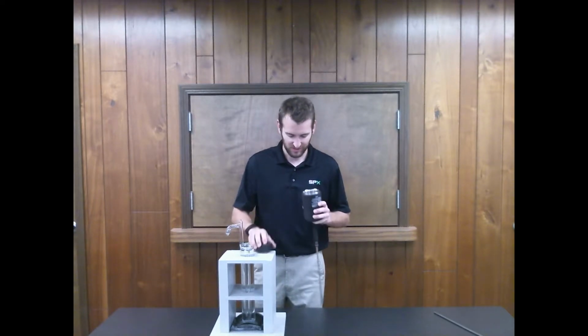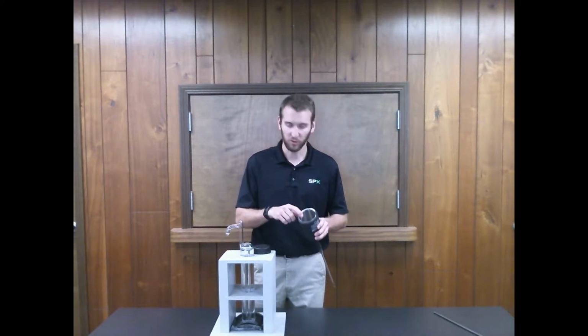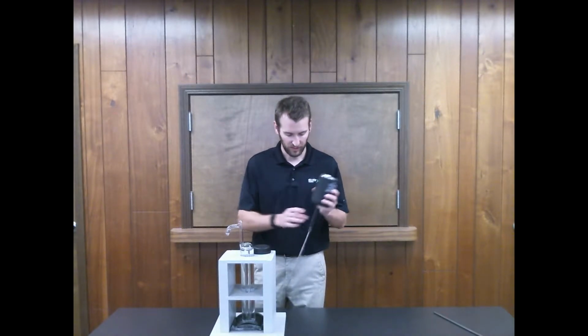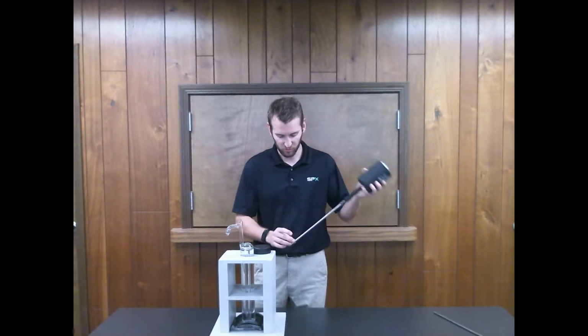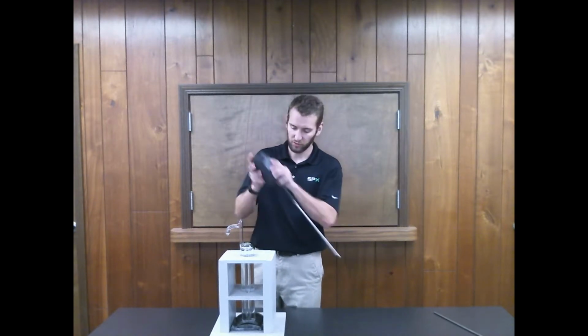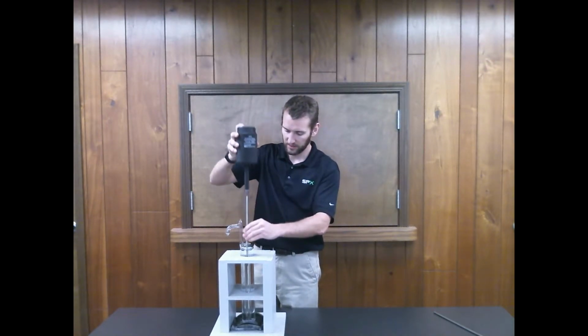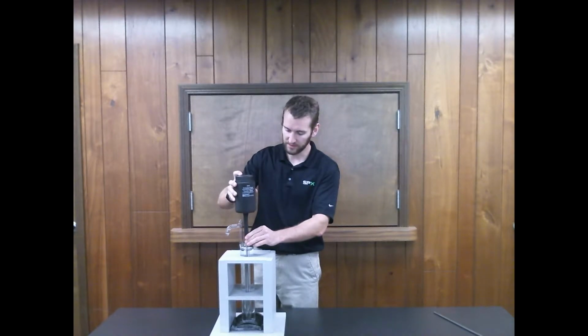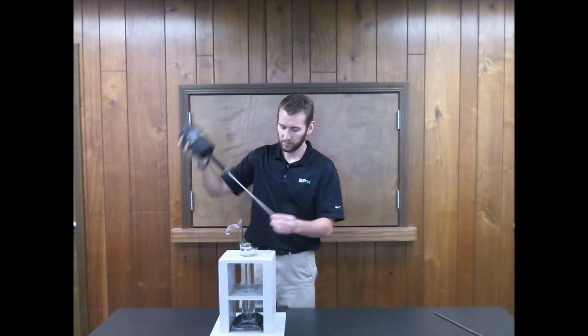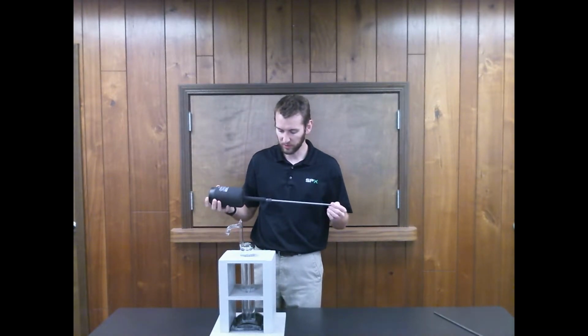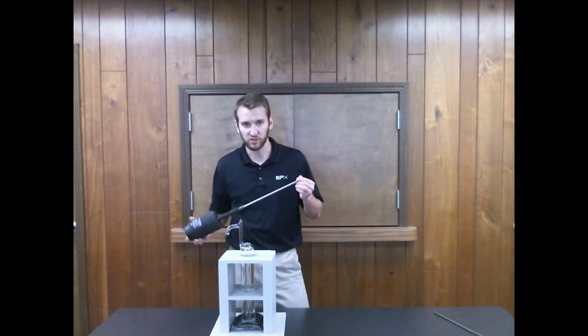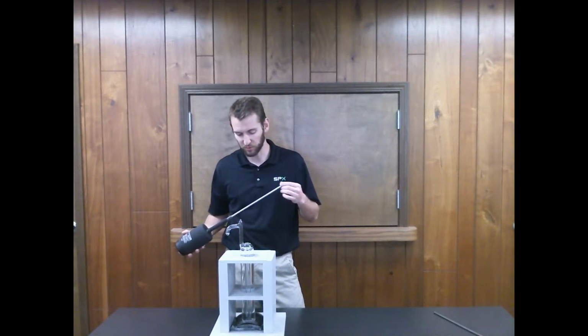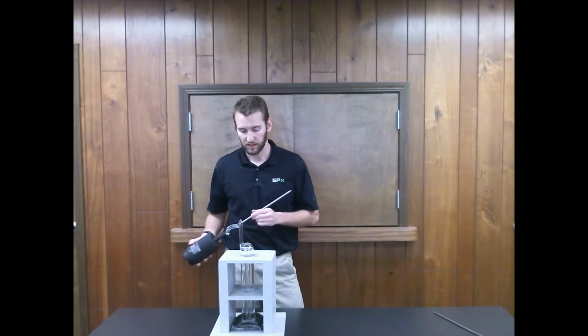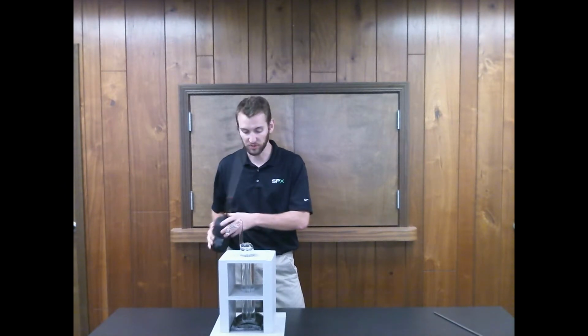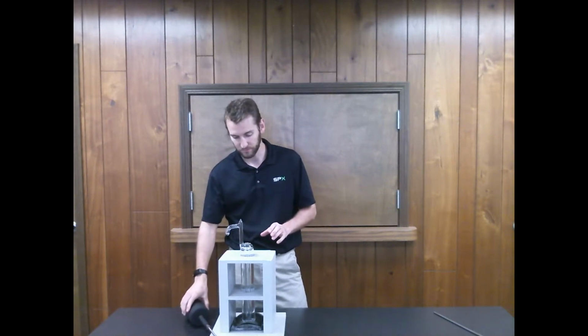How this works is you pour liquid nitrogen or crushed dry ice in here, and the temperature will be transferred down this tube. You would stick that into the well and let it set. This is the preferred method because you can remove the cooling quickly. So if you were making the mantle too large and it started pressing on the outside walls, it would cause it to crack, which you don't want, since that would break your triple point cell.